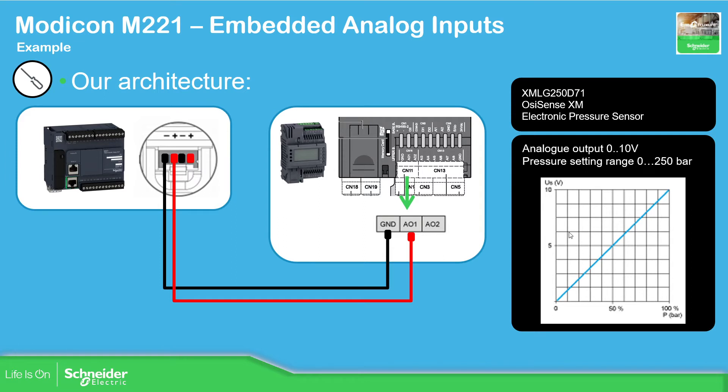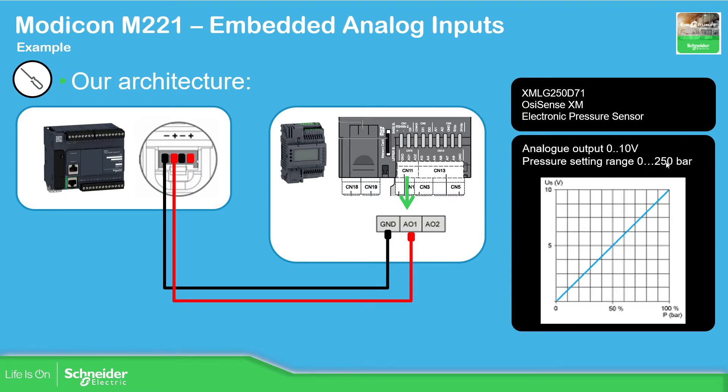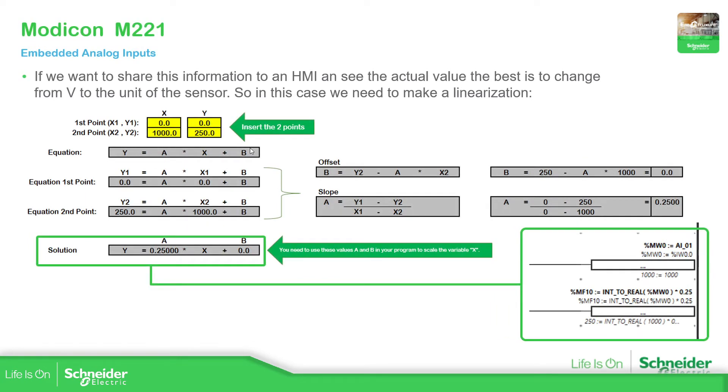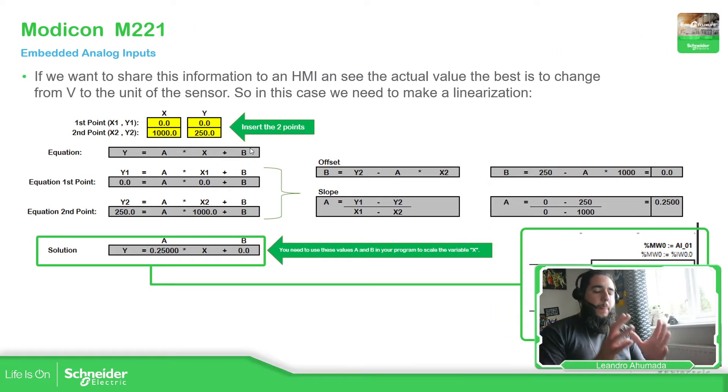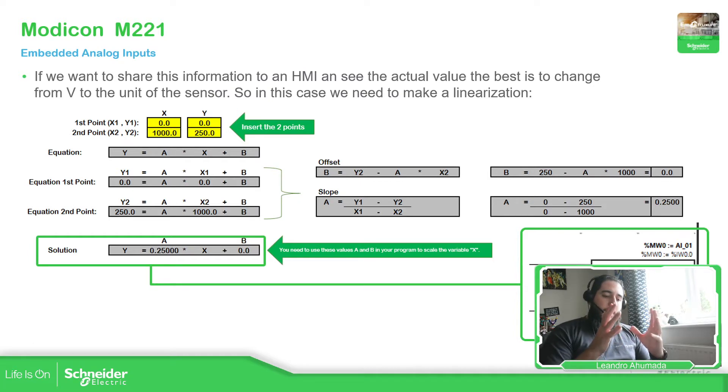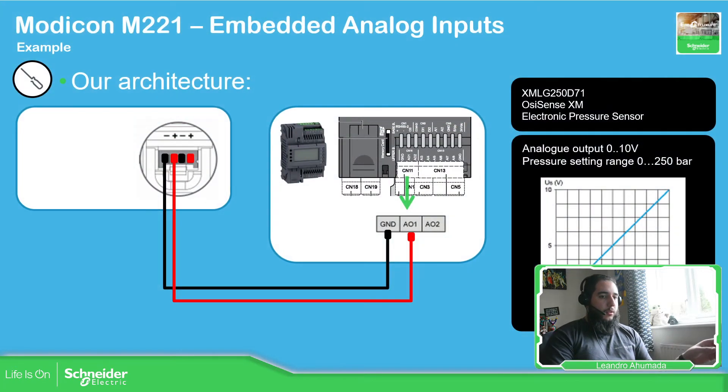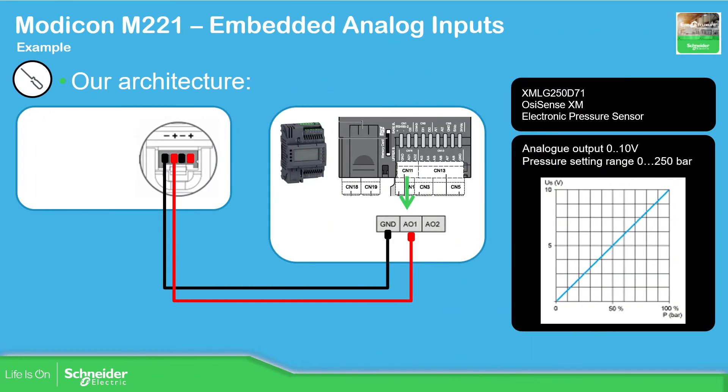The idea would be to see from 10 volts when I receive the 10 volts, the maximum range. In this case it's linear, the response of the sensor, so it will be very straightforward to calculate the bars to visualize in the HMI or other place. This is very important. As the output of the sensor that we have has a linear response, as I show you in this graphic, we can make a linear linearization.